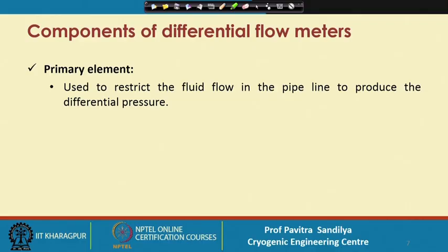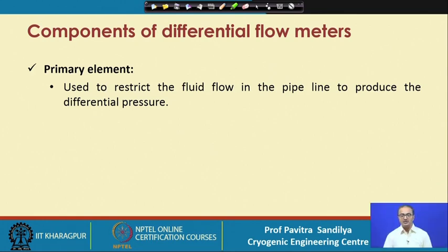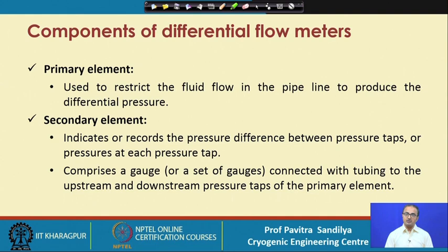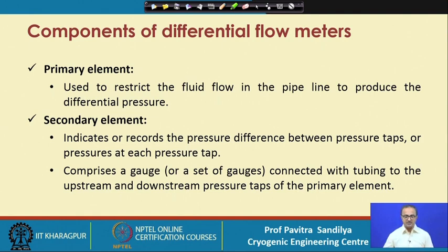We have a primary element — this is the element which restricts the fluid flow to produce the differential pressure across a finite pipe length. Then we have a secondary element, which records or indicates the delta P caused by the restriction. This delta P is measured across some pressure taps provided on the pipeline, and it consists of some kind of gauge or set of gauges.